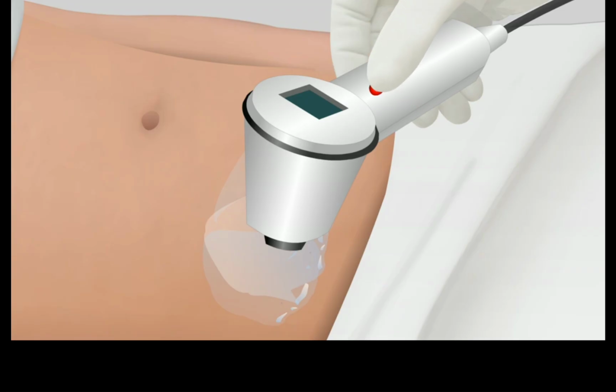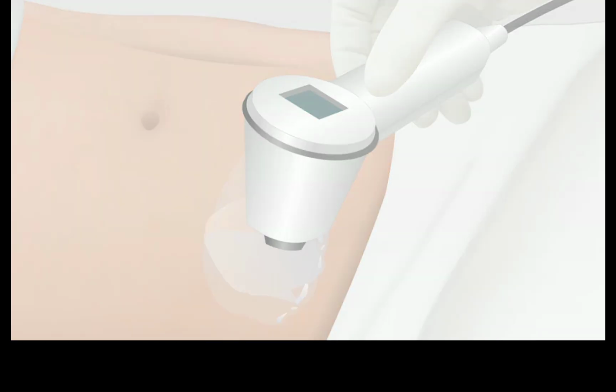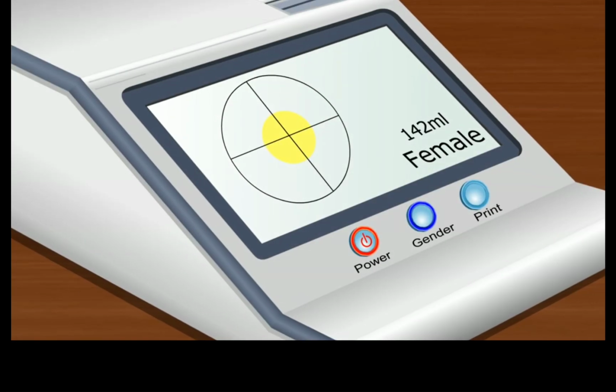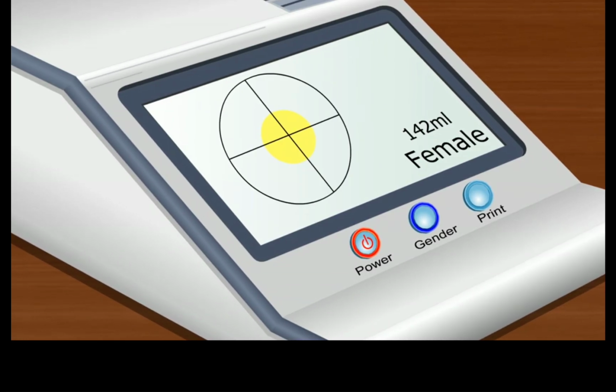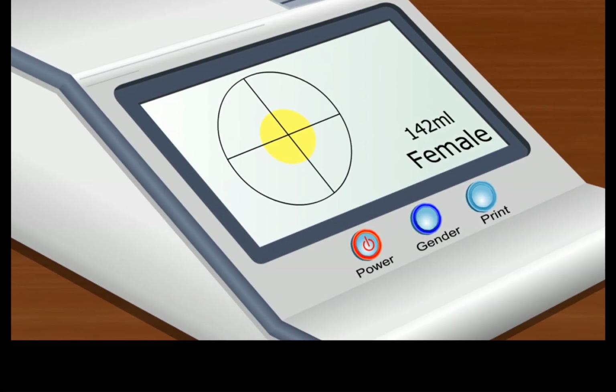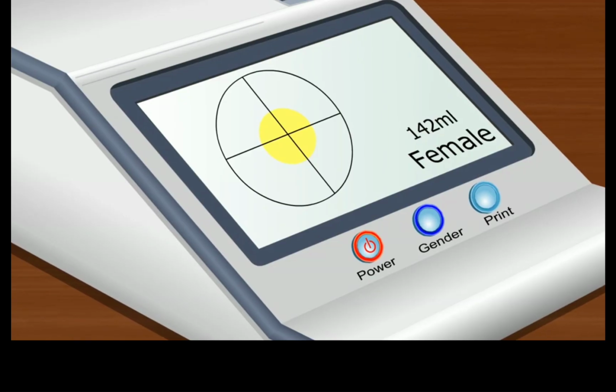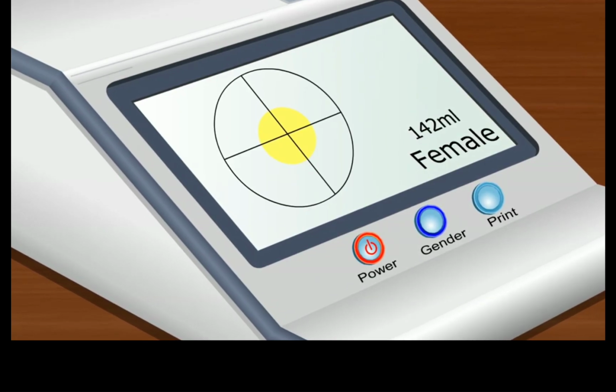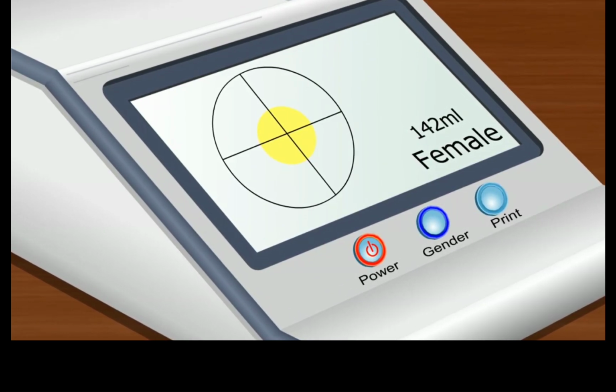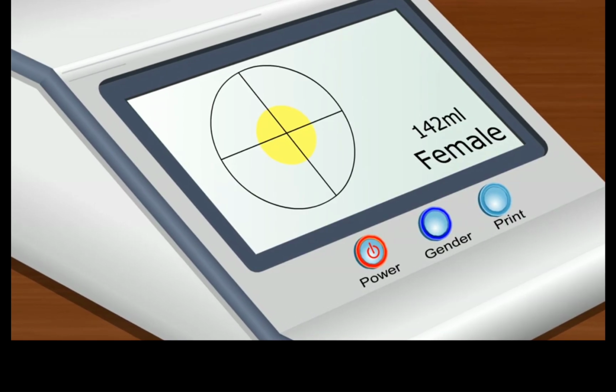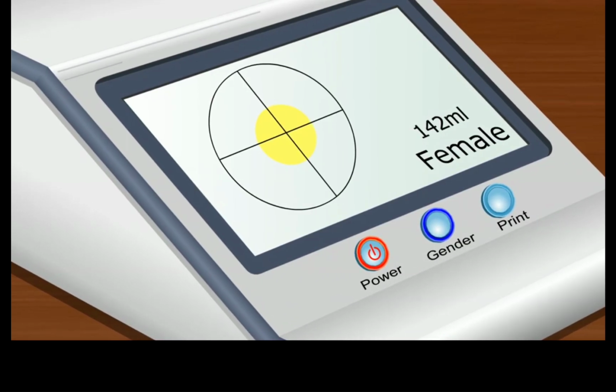Press the scan button on the probe and hold it steady until the scanner beeps. The volume measured will be displayed. In some scanners, an aiming screen with crosshairs will be displayed, with the light area on the screen representing the bladder. The crosshairs should be centered on the bladder, indicating an accurate probe placement. Other scanners use an ultrasound bladder image on the screen to assist in probe placement.